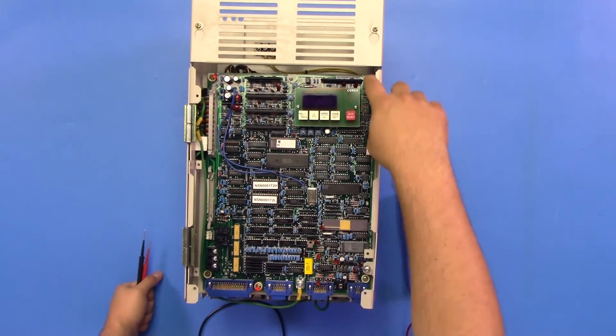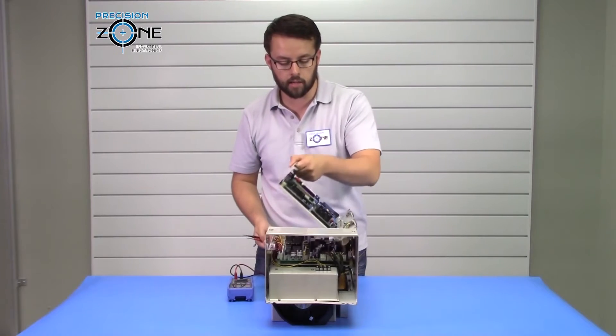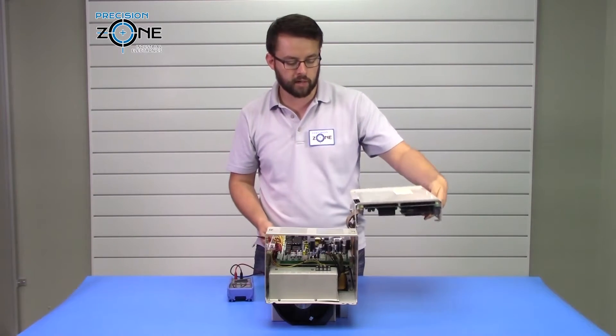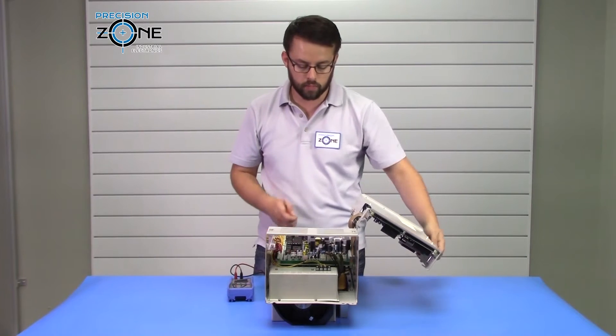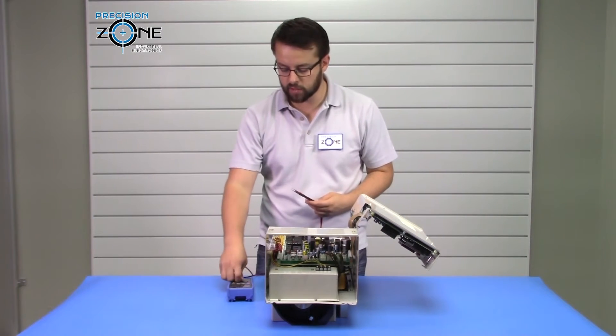To begin, you want to remove these two screws. Just undo them and they'll become loose. You can then lift this cover up and carefully place it to the side of the drive. You want to verify that the DC bus has been discharged.